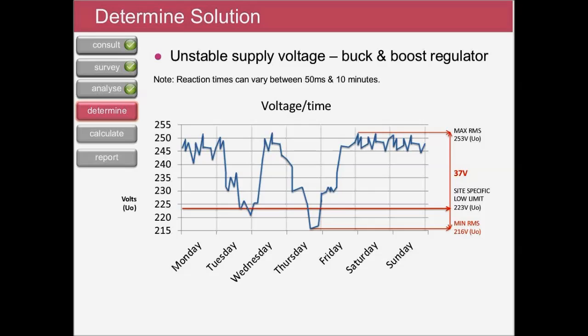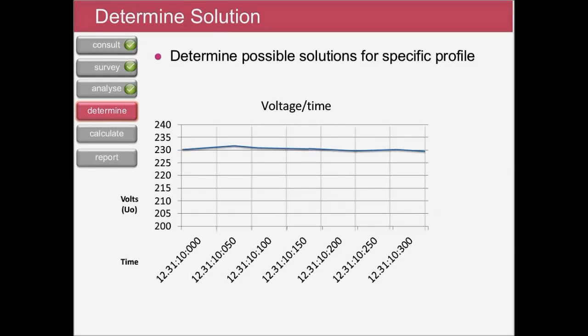However, as the automatic reaction time of these units can vary between 50 milliseconds and 10 minutes, and in some cases more, it's important to understand if any load-bearing equipment on site is likely to fail from a temporary loss in power that the voltage management hardware can simply not boost quickly enough. So this can be explained using another simple voltage time graph. You'll note the scale along the horizontal axis now divided into smaller 50 millisecond increments.